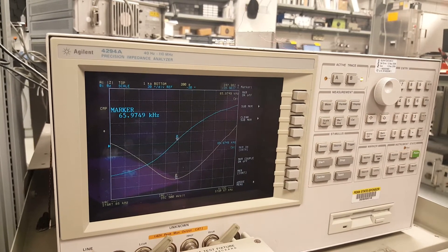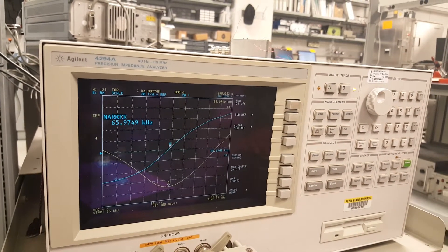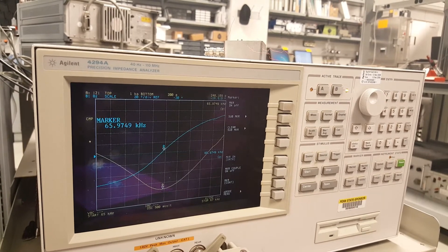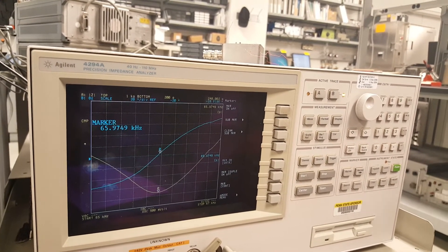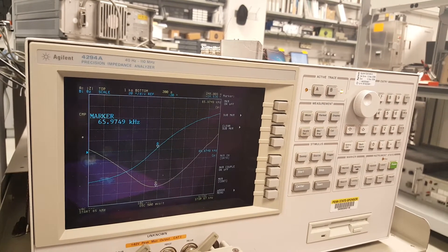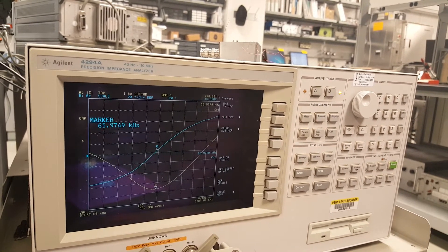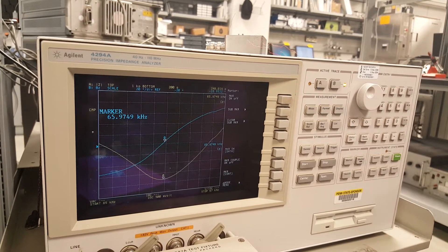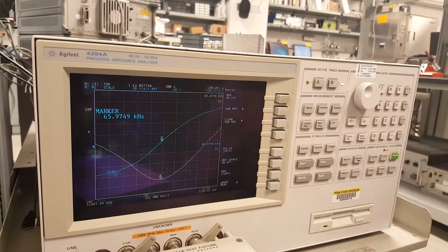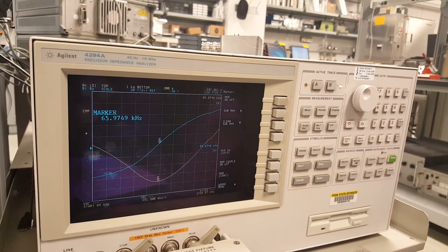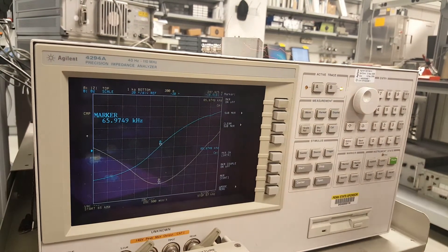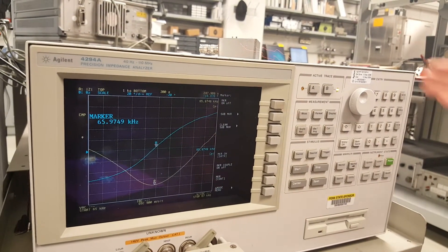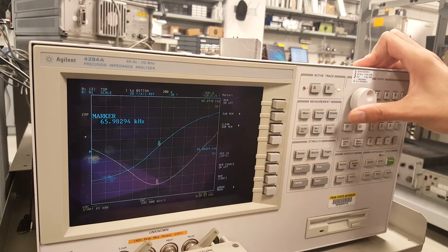What you will want to do now is, because whenever you take data from this machine, it gives you 200 points. If you take the whole thing, you'll get all this, you won't get enough resolution. You understand? You won't get enough resolution. So even if you normally don't have your exact 45 degrees or you don't have your exact bandwidth, you sort of interpolate between the two impedances to find the frequency. But you can't do that if you have really bad resolution. You want to have a finer resolution at this point because this computer only takes 200 points. This is a limitation of the machine, this is how they programmed it.